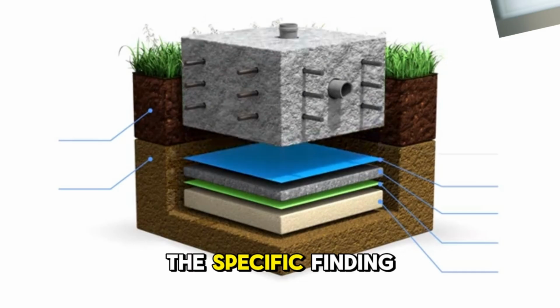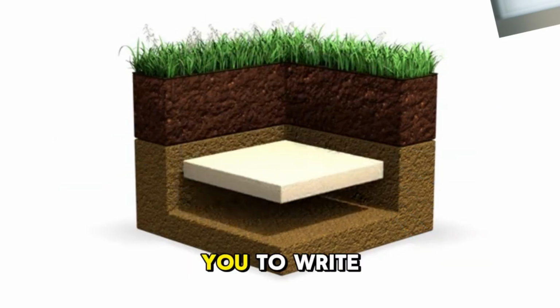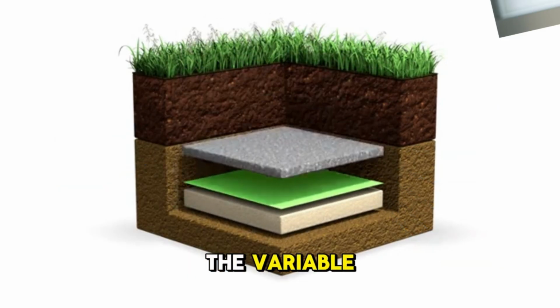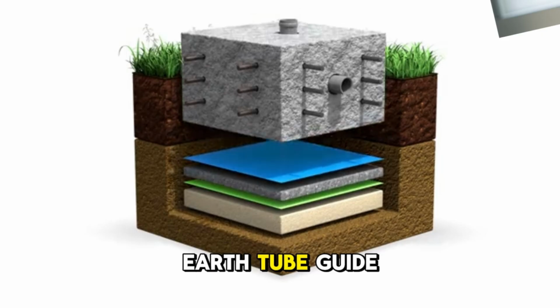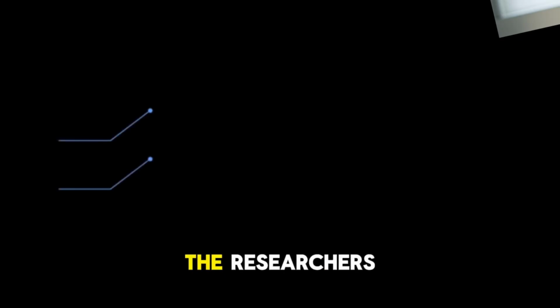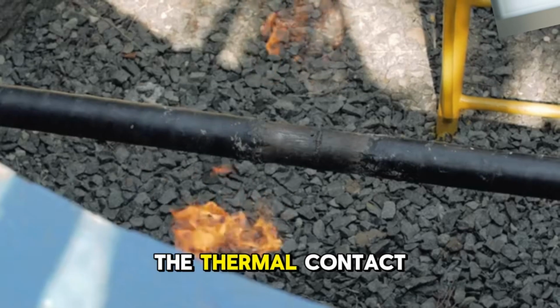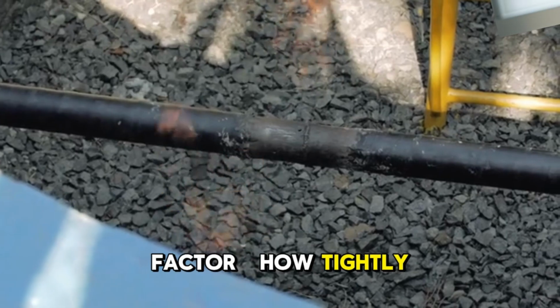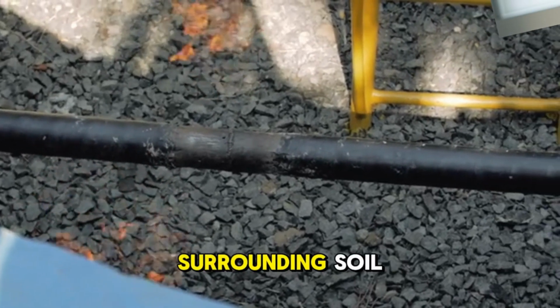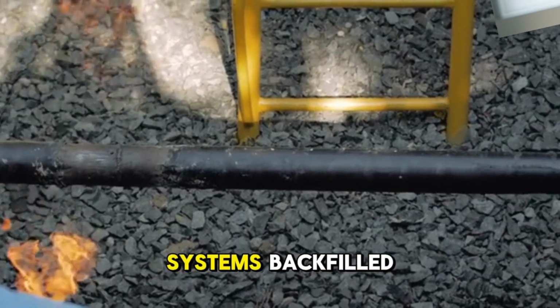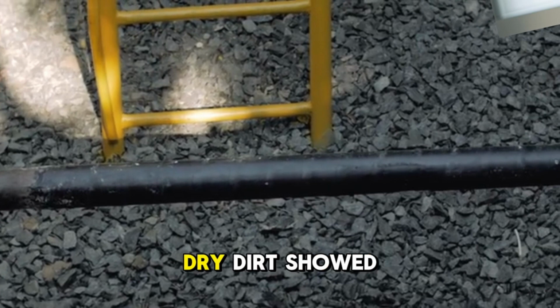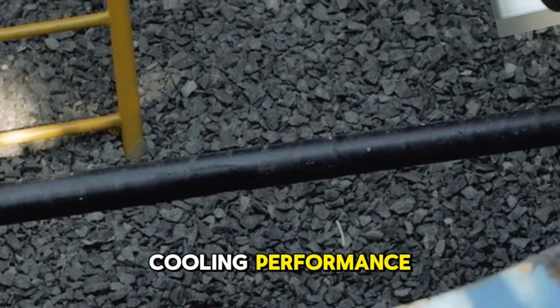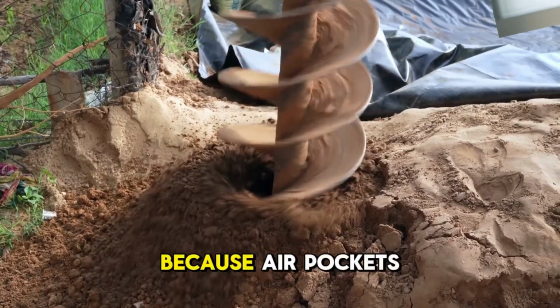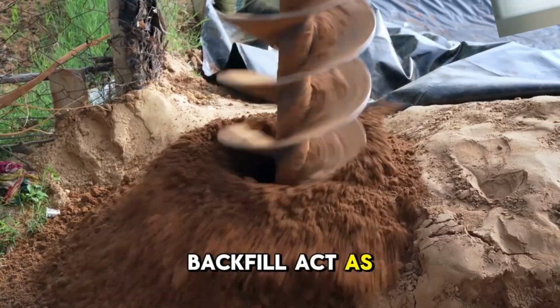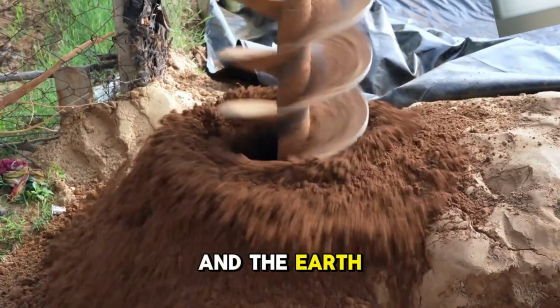But here's the specific finding inside that paper I want you to write down, because it is the variable that nearly every modern earth tube guide ignores completely. The researchers measured something they called the thermal contact factor - how tightly the pipe makes physical contact with the surrounding soil. Systems backfilled with loose gravel or dumped dry dirt showed cooling performance reduced by up to 40%, because air pockets in the backfill act as insulation between the pipe and the earth.